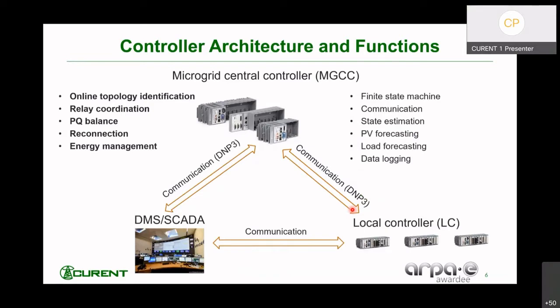To fully leverage the flexibility brought by the smart switches, we have designed and developed a scalable and open-source microgrid central controller based on National Instruments CompactRIO and LabVIEW platform. We also innovated unique functions crucial for the operation of this flexible microgrid, including online topology identification, relay coordination, PQ balance, reconnection, and energy management. We also realized other functions that are integral parts of the controller, including the finite state machine, communication, state estimation, PV and load forecasting, as well as data logging. We also established communication paths to and from SCADA and also to the local controllers of the DER.